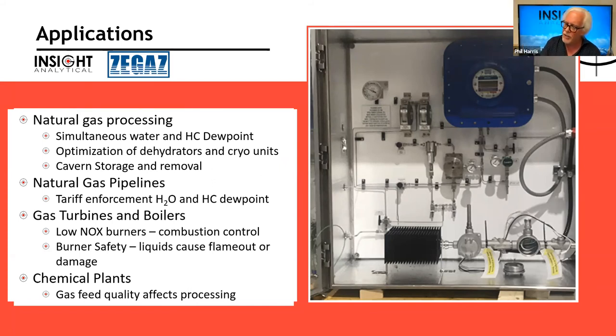Natural gas pipelines have tariff enforcements on both water and hydrocarbon dew points. Gas turbines and burners, low NOx burners especially, they want to get this in there for combustion control. If there's risks of hitting the dew point, those drops of liquid contain around 300 times more molecules than a gas at the same volume does. So the liquid consumes a lot of air. So if you're trying to do combustion controls, you want to have this in place. Liquids can also cause flameouts in burners and in turbines. Can overtemp heat turbines as well and damage turbine blades. And in chemical plants, gas feed quality, both water and hydrocarbon dew point, affect a lot of our catalysts upstream. So again, we want to be able to look at these four processing type applications.